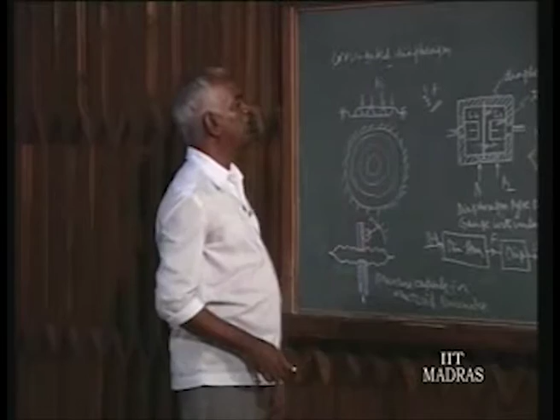So that restriction, 1/3 the thickness of the diaphragm alone it can deform, is overcome here by going for corrugated diaphragm. So you have got more deformations. Such an instrument is available in the aneroid barometer, which is in aeroplanes flying at different heights, where the atmospheric pressure at that level acts over it. This is called a pressure capsule, made up from two such curved diaphragms. This is one curved diaphragm, this is another one. Bring both of them together, and at the circumference, you solder or weld it, so it becomes a capsule. And then when you apply a pressure, the capsule expands.